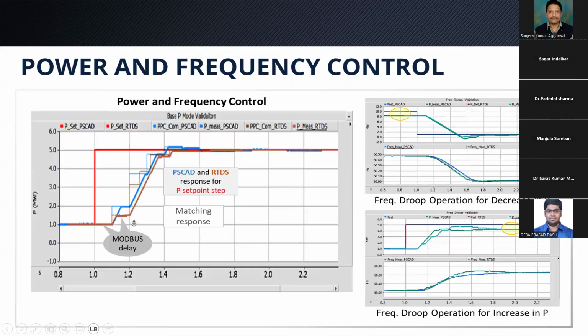Another thing we'll notice here is that PSCAD is an instantaneous value simulation, whereas RTDS is also an EMT simulator, an instantaneous value simulator. But the device is a physical device, which is using a communication protocol. That communication protocol is called the Modbus protocol, and it's a slower protocol. It typically operates in the range of 5 milliseconds to 1000 milliseconds.